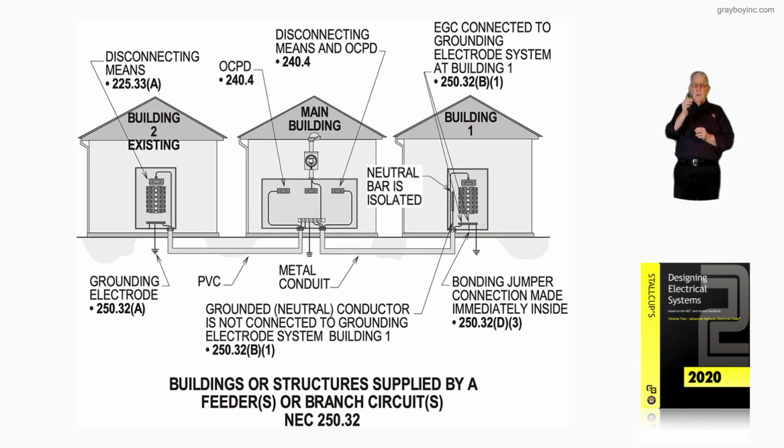But the 225 amp main would require that equipment ground routed over to building 1 to be a number 4 based upon the 225 amp main, because we have an overcurrent device ahead of those conductors feeding building 1. So we have to use table 250.122 because it's considered load side. So the equipment ground would be number 4, but you could have a 1-aught, you could have a number 4, number 6 neutral, just depending on the amount of neutral load that you had.